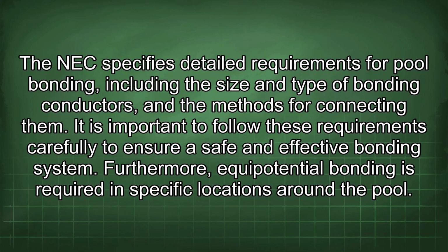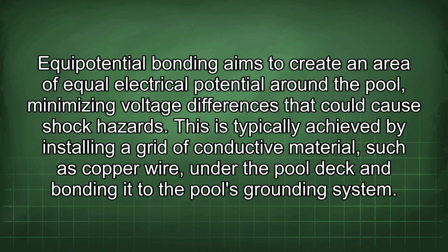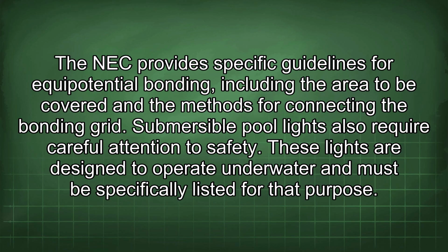Furthermore, equipotential bonding is required in specific locations around the pool. Equipotential bonding aims to create an area of equal electrical potential around the pool, minimizing voltage differences that could cause shock hazards. This is typically achieved by installing a grid of conductive material, such as copper wire, under the pool deck and bonding it to the pool's grounding system. The NEC provides specific guidelines for equipotential bonding, including the area to be covered and the methods for connecting the bonding grid. Submersible pool lights also require careful attention to safety.